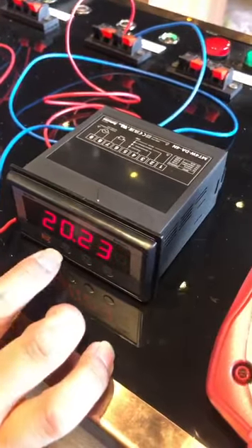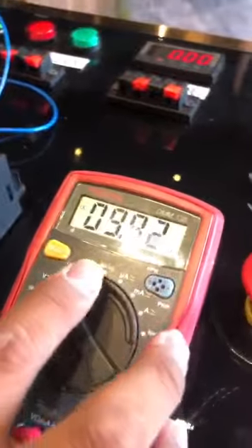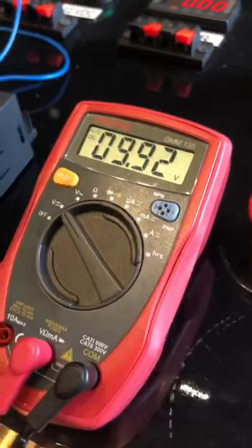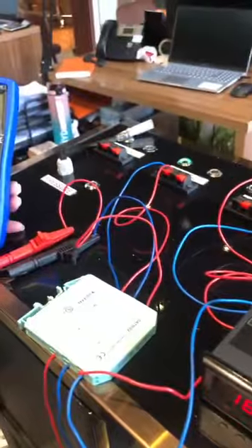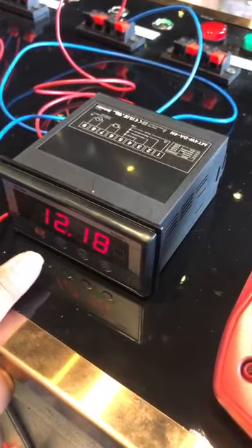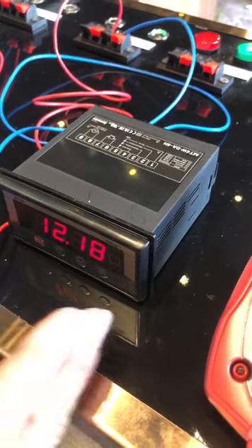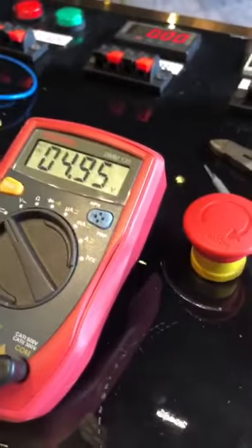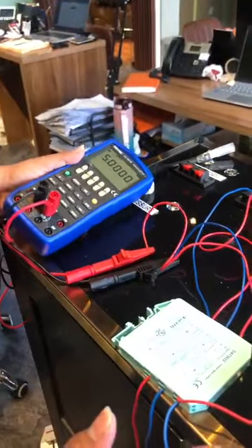So we got a 20 milliampere output, and we also got 9.92 volts, which is almost the same. If I make it half, like 5, we got 12 milliamperes, which is half of the 4 to 20 milliamps, and we have almost 5 VDC, same as the signal source simulator. So again, this is working properly.